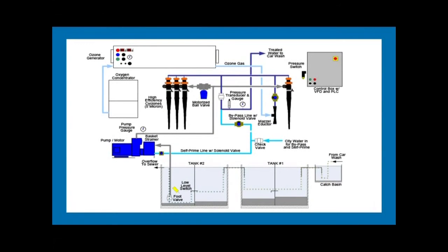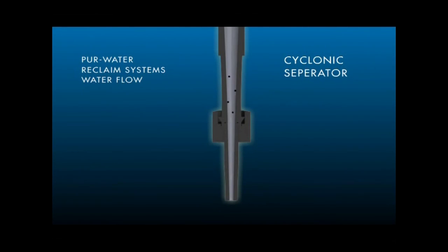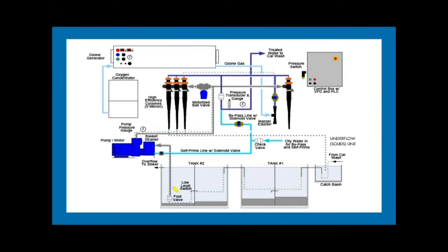The water now enters the Pur-Water system at the pump. Water is pushed into the cyclonic separator. The balance of the water solids spin down the separator and out the underflow line. Clean water goes to the recirculation line where it is joined by ozone. From here, the clean water returns to the holding tank through the recirculation line.